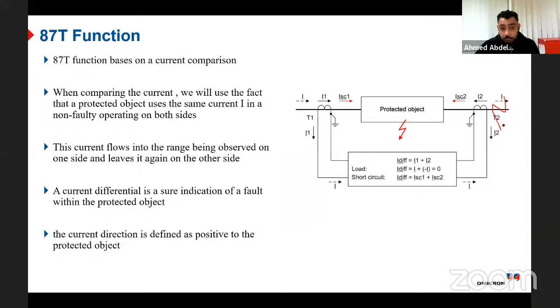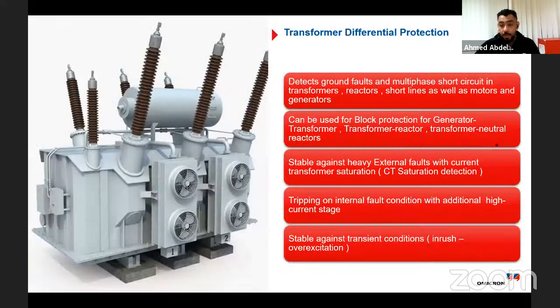If I have a fault here, say it is outside my protected zone, my system should be stable. So the differential protection should be stable against the external fault. And other phenomena might appear during the external fault, because I can have an external fault very close to the CT, and the CT might be saturated.